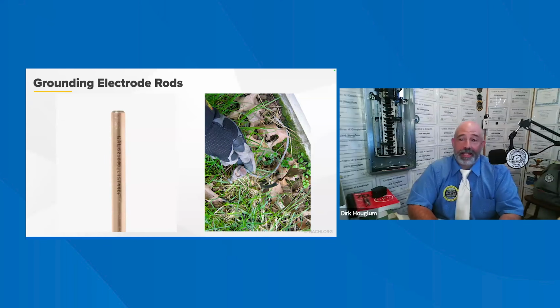shall be at least 5/8 of an inch in diameter. Grounding electrodes of a pipe and conduit must be at least 3/4 of an inch, metric designator 21. There are special listed rods, and listed rods may not be less than 1/2 inch in diameter. If pipe or conduit is used as a grounding electrode, it must also be no less than 8 feet in length and no smaller than trade size 3/4 of an inch.